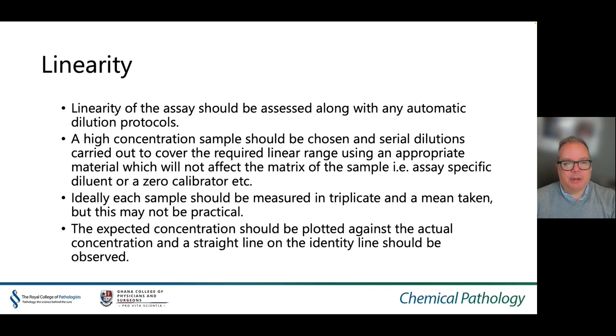Linearity of the assay should be assessed along with any automatic diluting protocols. A high concentration sample should be chosen and serial dilution carried out to cover the required linear range, using an appropriate material which will not affect the matrix of the sample — for example, an assay-specific diluent or a zero calibrator. Ideally each sample should be measured in triplicate and a mean taken. The expected concentration should be plotted against the actual concentration, and a straight line on the identity line should be observed. If not, an explanation should be sought.